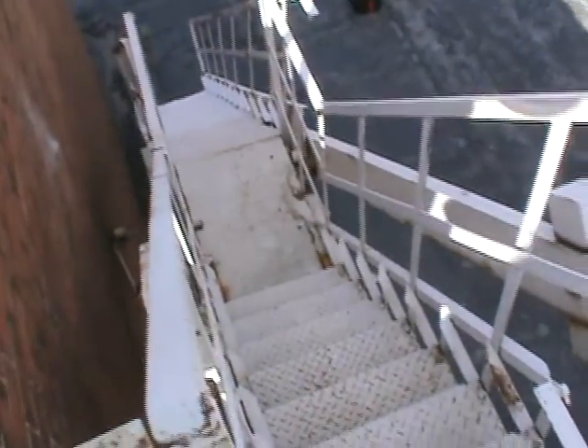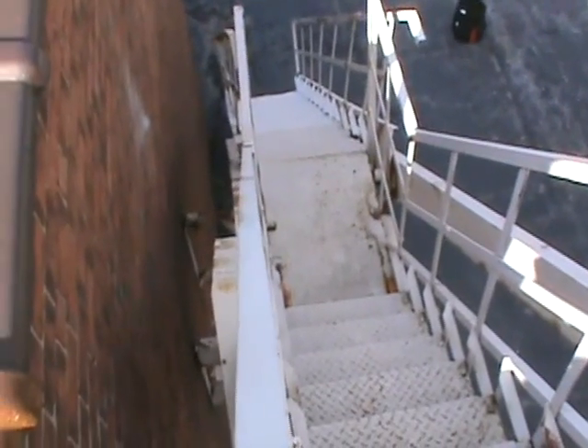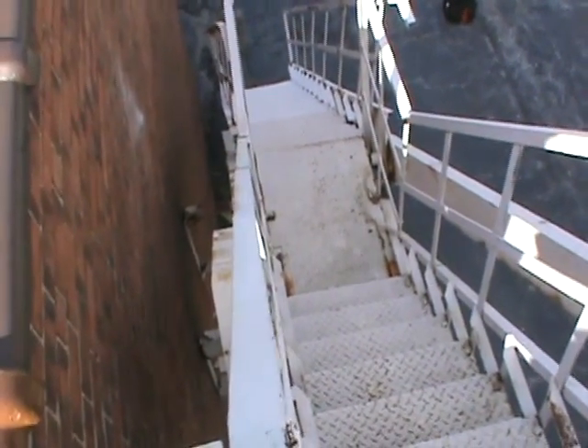It's got too many structural issues. So with original hardware everywhere, you have a choice: spot repair this fire escape, then load test it, or you can fully refurb this fire escape, and this one is in that category. Fully refurb, there is no load test for the next 15 to 25 years. You still must do the examination every 5, but you'll have other evidence of strength.